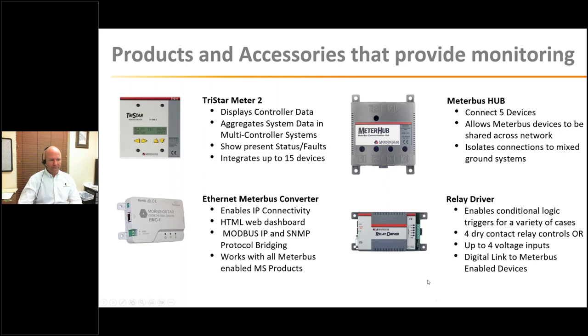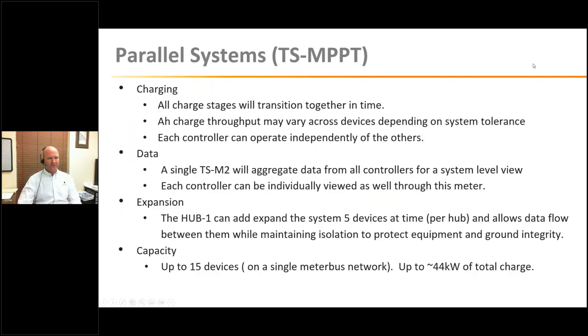Going forward, a few comments about parallel systems, just want to touch on a few topics here. When the TriStar MPPTs are used together, they're connected with the meter bus interface and the hub and the meters. All of the charging stages of these controllers, since they're all looking at the common battery voltage and are very sensitive in terms of their voltage accuracy, will transition together.